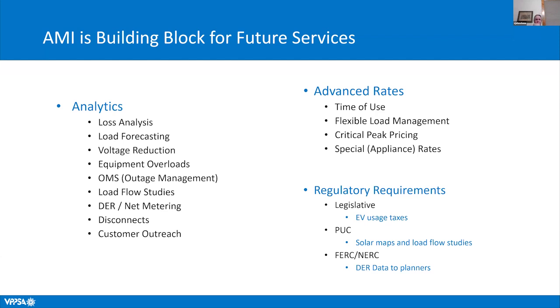People call after it's restored. This allows you to, you have to work out the operating procedure for who can do it under what conditions, but you can ping the meters to say, oh, a person called and said they're out. I'm going to send a signal and see if the meter responds. That'll let you know either they're wrong or they've got a breaker issue inside their house. And it's not you. But from a customer service standpoint, you can tell the customer, it's not us, it's you.